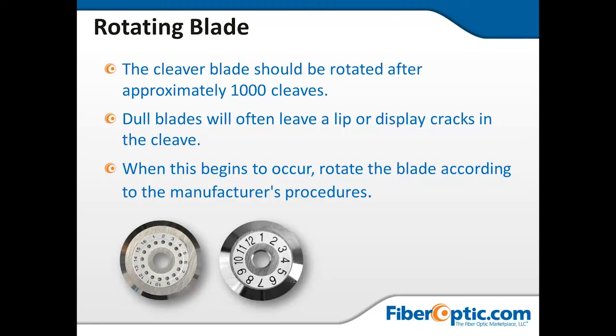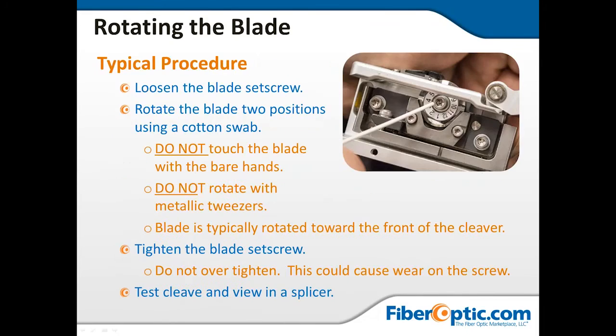Typical procedure for this cleaver: loosen the blade set screw. Rotate the blade 2 positions using a cotton swab. Do not touch the blade with bare hands. Do not rotate with metallic tweezers. The blade is typically rotated toward the front of the cleaver. Tighten the blade set screw. Do not over tighten. This could cause wear on the screw. Test cleave and view in a splicer. This is the only way you will be able to test and see how well your cleave is.